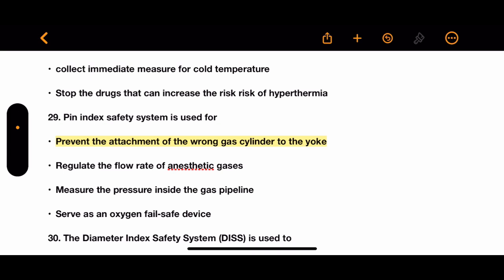Question 29: The pin index safety system is used for which purpose? Options: prevent the attachment of the wrong gas cylinder to the yoke assembly, regulate the flow rate of anesthetic gases, measure pressure inside the gas pipeline, or serve as an oxygen fail-safe device. The correct answer is to prevent the attachment of the wrong cylinder to the yoke assembly.